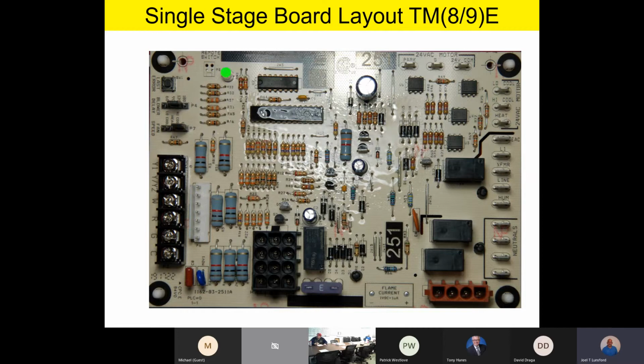So if everyone can take a look, the board that we're looking at is a typical TM8/9E control board. This is going to be a single stage heating and up to 2-stage cooling capable board. It has been a very reliable board for us. It's been a good board for us. If you had a board in front of you and oriented it, this is what it would look like. The other thing I want to point out is that we don't have any wires on the board. This is strictly to look at the layout of the board without the benefit of the wires hooked up to it.